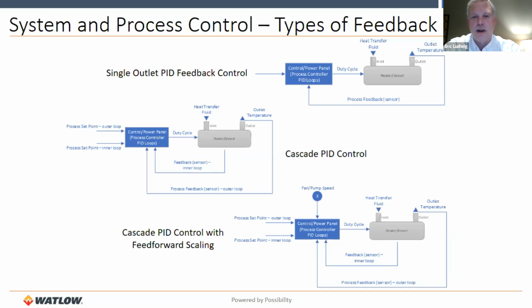In the center diagram, we have what's called a cascade PID control. The advantage of this is that it puts an additional sensor inside of the heater or the vessel itself, and you're actually controlling two loops. One is the outer temperature, so that the outlet temperature is met, but the other one is an internal temperature. And typically that's on the heater sheath itself to ensure the reliability of that heater and also ensure the reliability of the fluid passing through the heater. In that particular case, you're preventing the fluid from overheating and preventing the element itself from overheating. So it controls not only the outlet temperature, but also the inside temperature within the actual heater itself to ensure certain limits aren't exceeded. So there are some advantages of the cascade PID control loop right there.